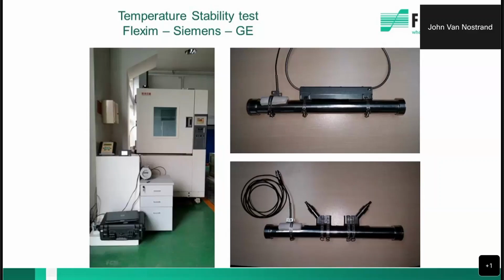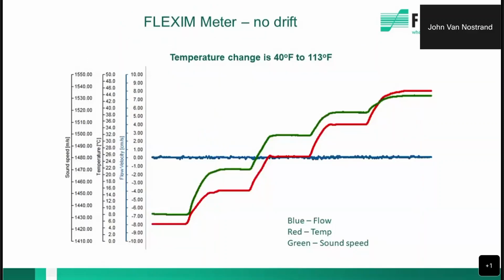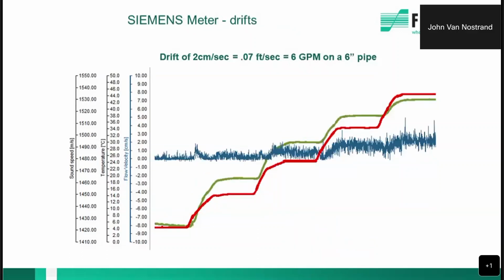And what we've done here is a temperature stability test in a controlled environment with an oven and two other major competitors that we value as competition. Taking a look at the FLEXIM meter over time, what we're looking at is a temperature change from 40 to 113 degrees Fahrenheit. This is a typical summer or fall day in Florida. It could get quite hot in the afternoon and could cool off in the evening, or any part of the country. And what we're looking at here is that blue line being the output from the meter. The red line is the temperature change, and that temperature changes, like I said, from 40 to 113 degrees. And then the green line is the sound speed of the media. We also know that that changes along with temperature, and we track that. And it's important to note that because we'll talk a little bit more about that in a moment.